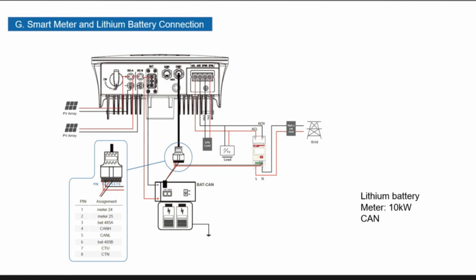Oh, if you use lead-acid batteries, you do need to have a temperature sensor that you put onto the batteries that you then wire back to the inverter. I don't suppose any of you will use lead-acid batteries, but you do need a temperature sensor if you are going to use them. Now you're talking about the lead acid, so you don't have any communication between the battery and the... No, just a temperature sensor on there, that's it.